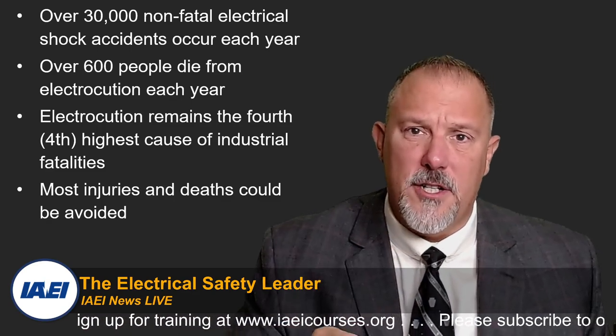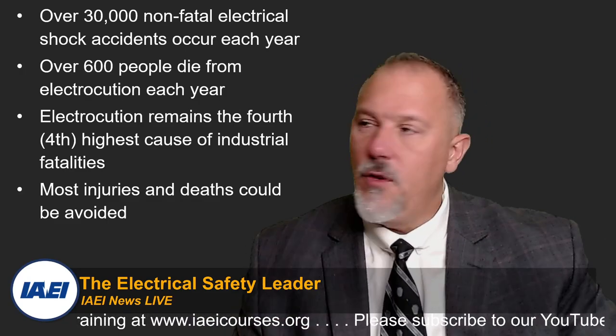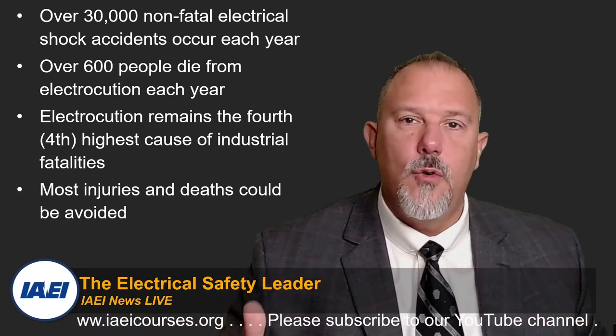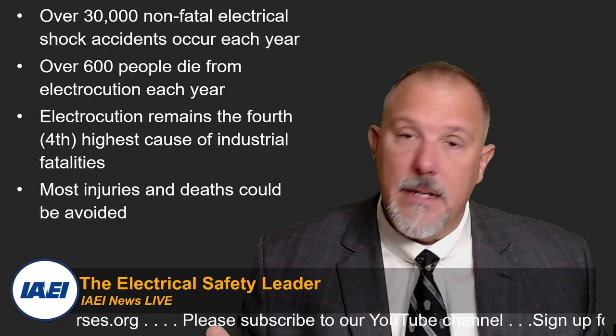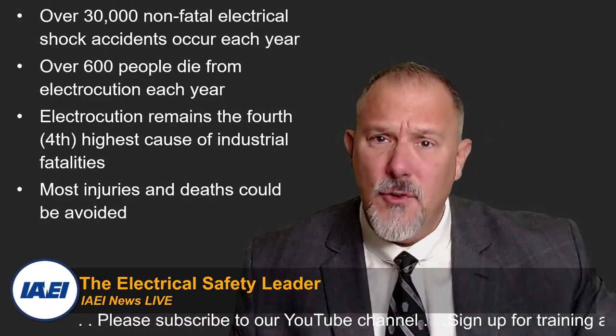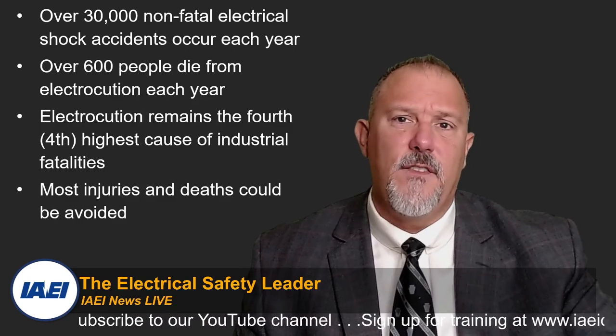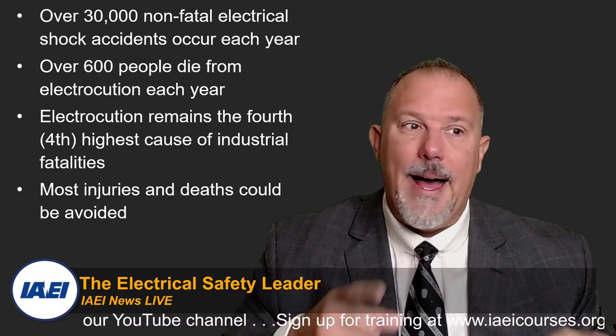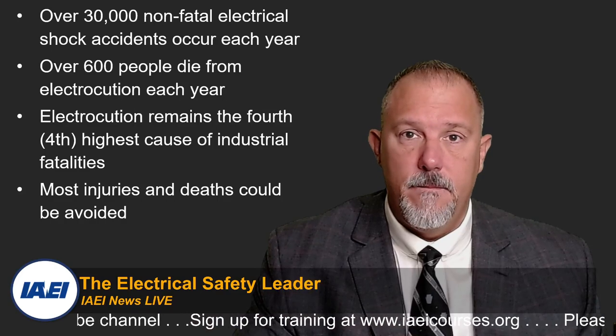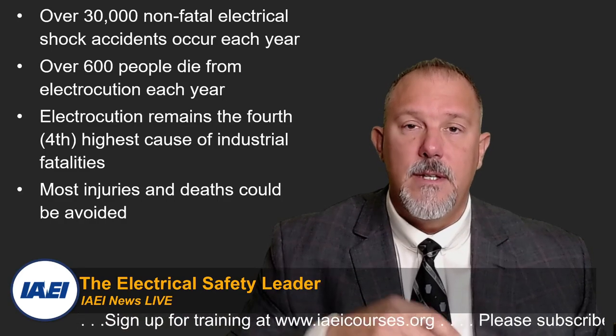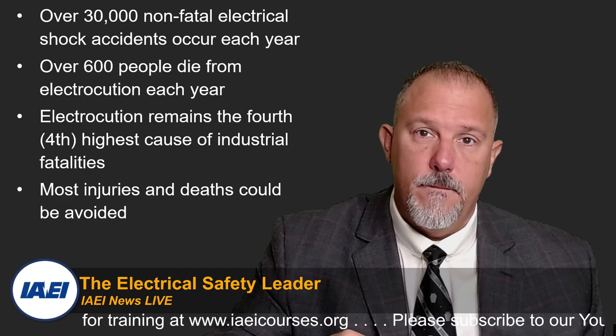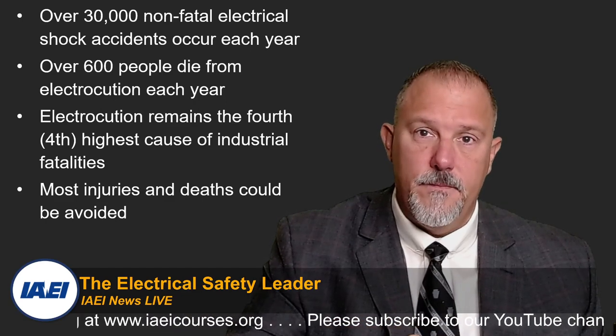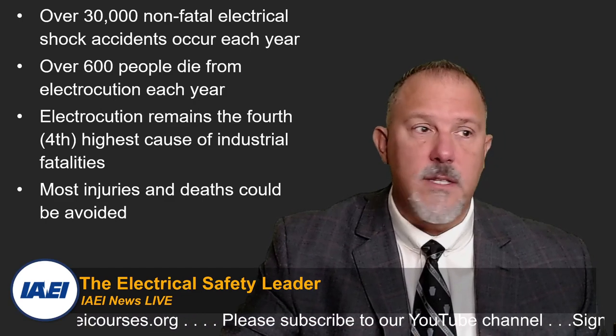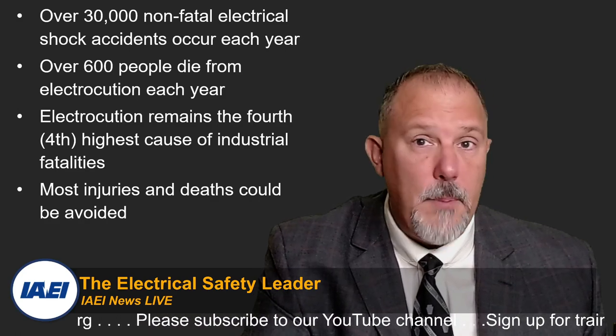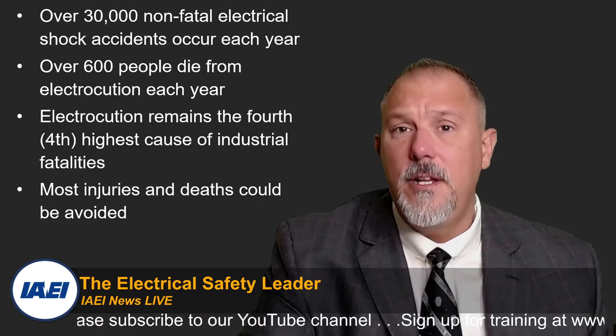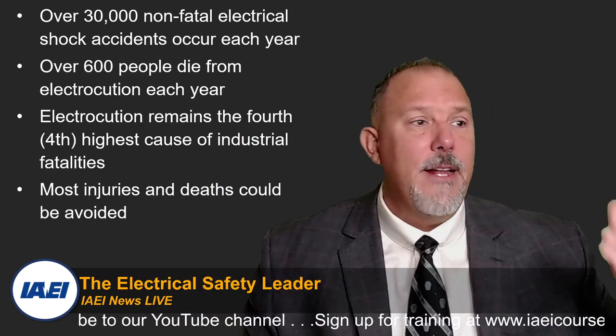I don't want to say work condition, because you may not be working on it. If you walk up and you see an electrical appliance damaged and it's plugged in, you're not going to work on it. You just want to establish an electrically safe condition. You need to know, how do I safely neutralize this hazard? It might be that you can simply unplug the appliance. It might be you don't want to unplug it. It might be that you need to go down to the circuit breaker and turn it off.